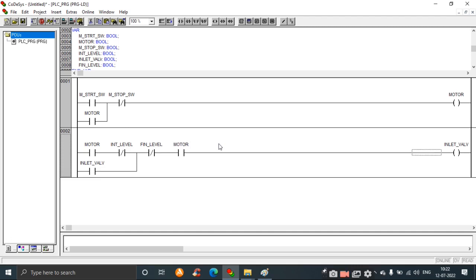We need to connect the motor here as a parallel contact so that whenever the M_start_switch is off, the parallel line keeps the motor on. For the second rung, we have taken a contact and a negative contact for INT_level — that is, the intermittent level. Whenever this switch is open, the intermittent level is filled. The next switch, FIN_level, when open, means the final level indicator is active, meaning the tank is full and the motor should be turned off to stop water flow.